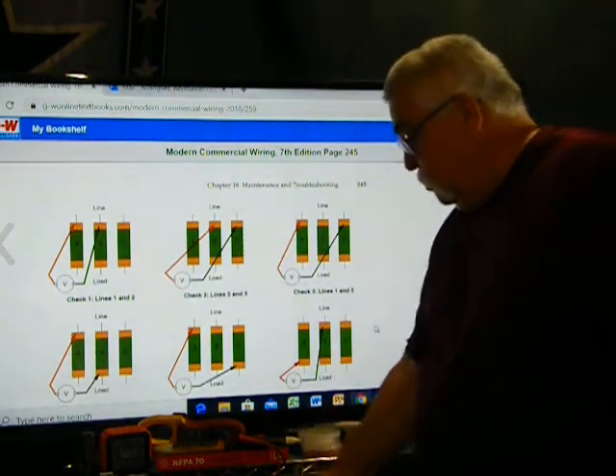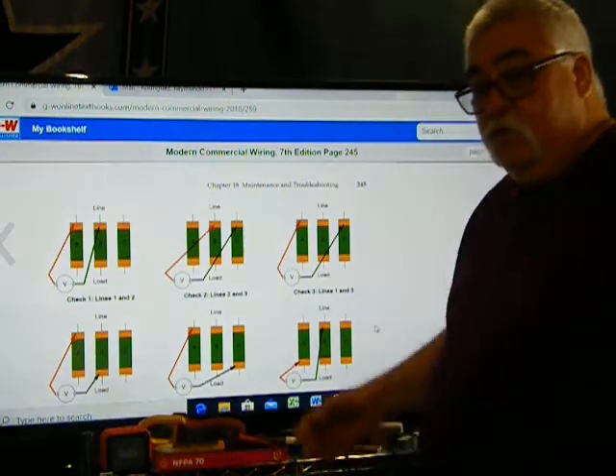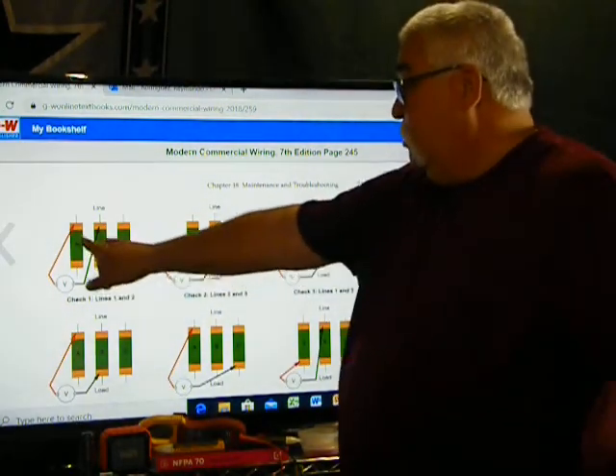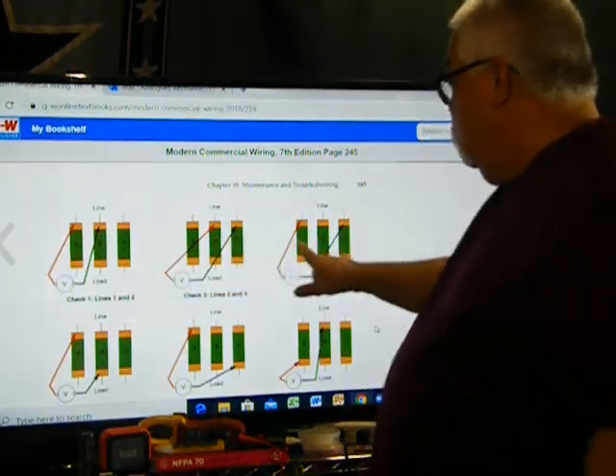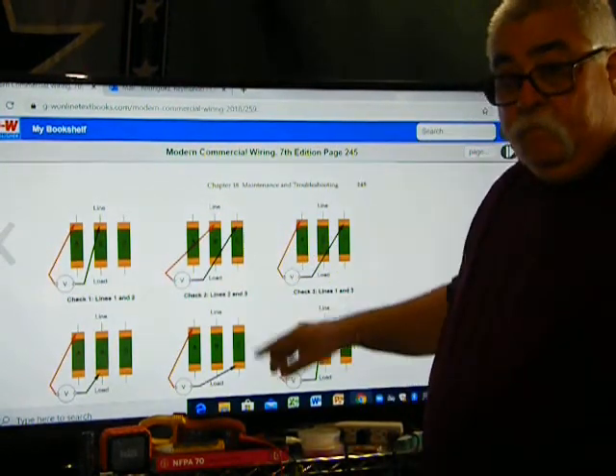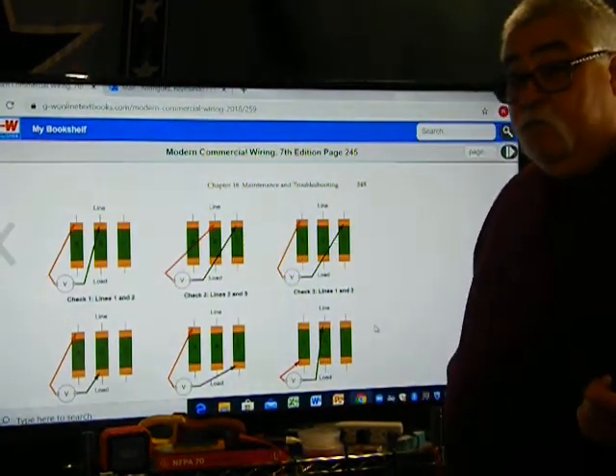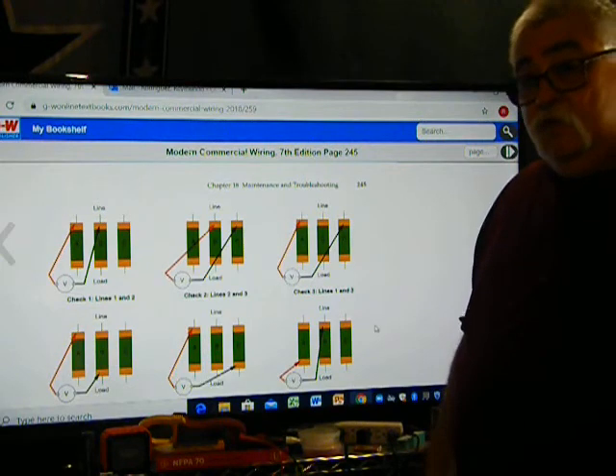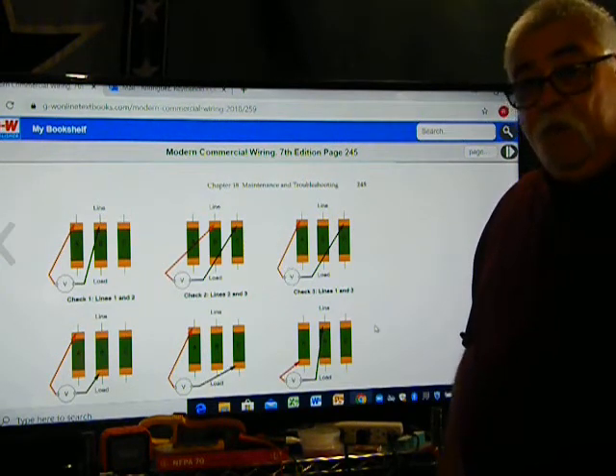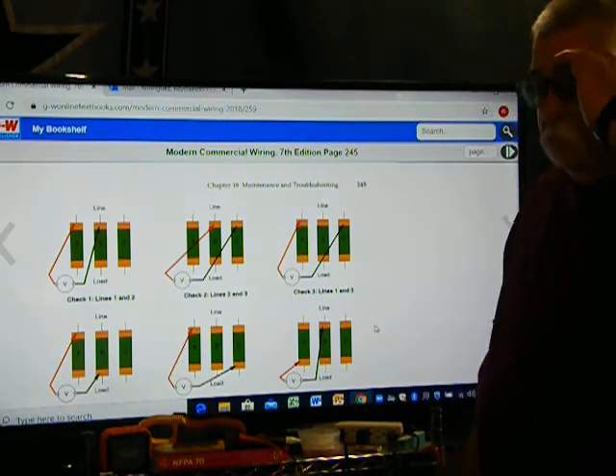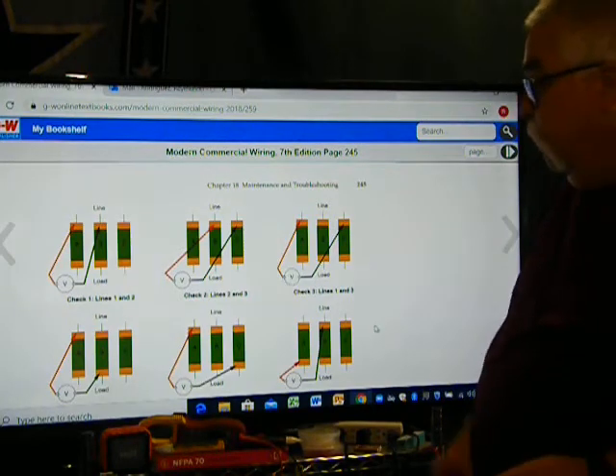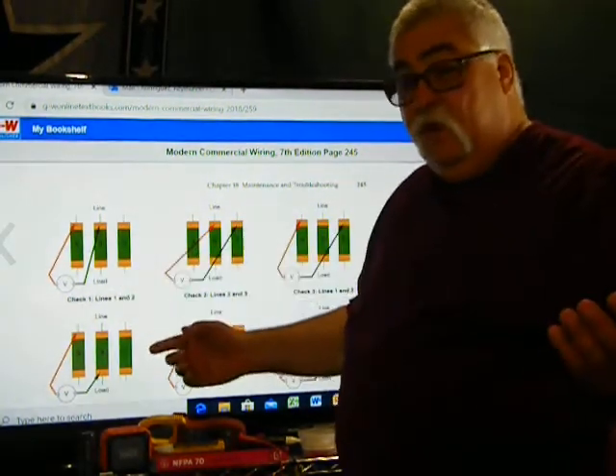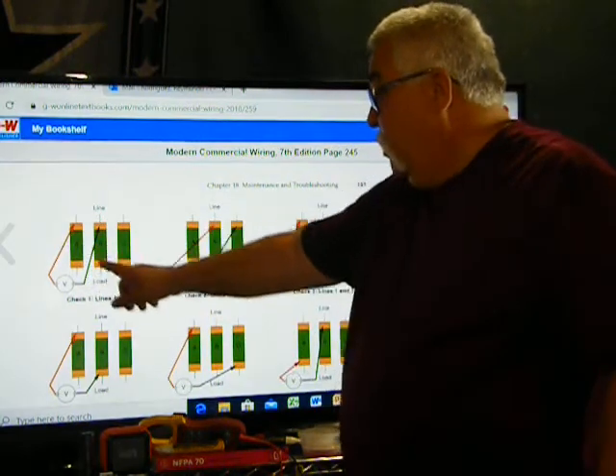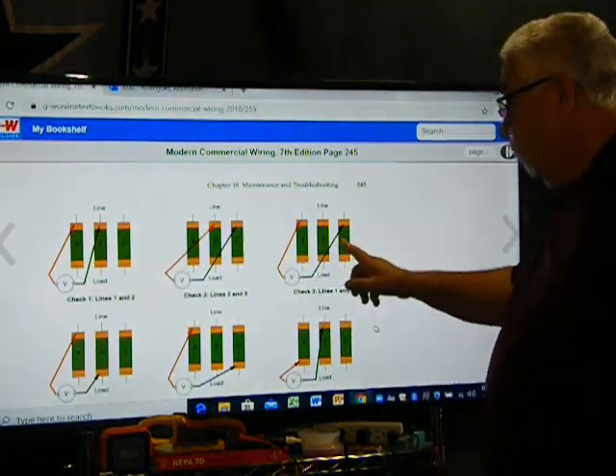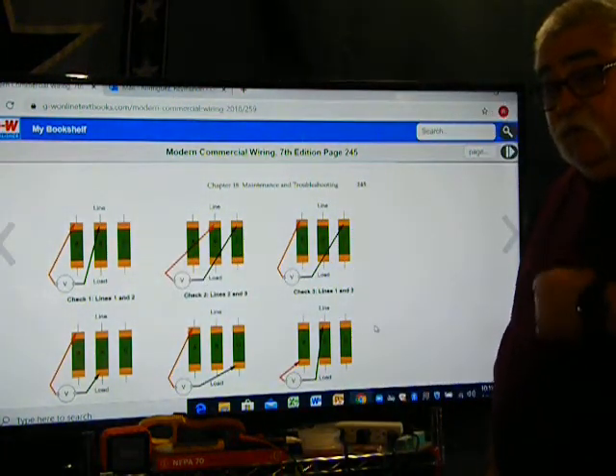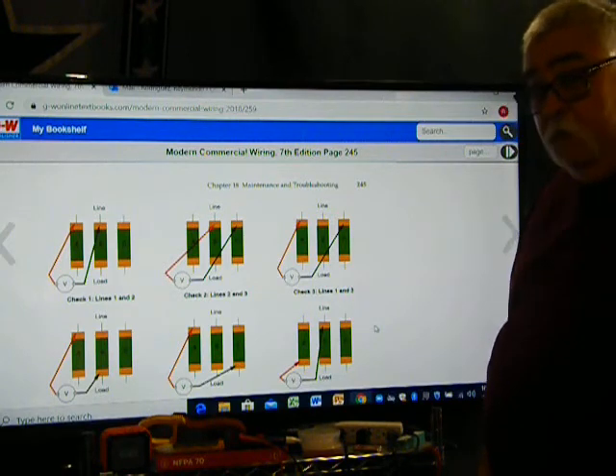Okay, so you get your tester, and you're measuring across. So you should get the same voltage here as here and here. Okay, you should get the same voltage. If you don't have the same voltage, then something's wrong in your supply, so coming out of the panel or distribution, there's where the problem may lie. So your voltage should be the same. So this is a 480 volt circuit. I should have 480 here, 480 here, 480 here. Everything's okay. If I don't have that, then the problem is at the supply.